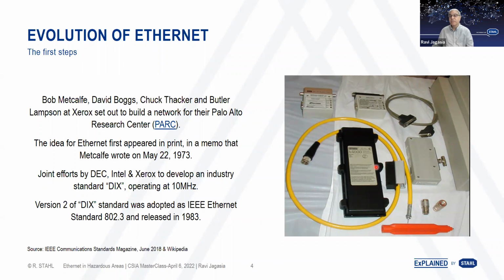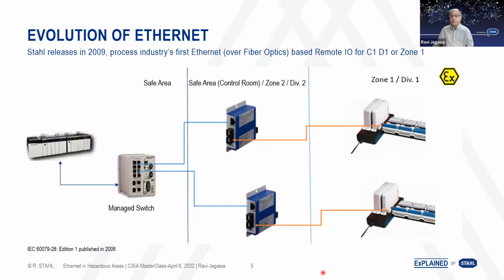Just some images here to realize what do we have or what we were working with previously when we talked about Ethernet and how compact the electronics is today. Going forward, STAHL did come up with a hazardous area solution with Ethernet, but with fiber optics. This was based on an IEC standard published in 2006, and in 2009 we came out with the first hazardous area installable remote I/O with an Ethernet interface, of course over fiber optics. So what you see is the fiber optics here, and then the standard cable going to the switch and going into your control system. This could be installed in zone 1 div 1, and these could be installed in the zone 2 div 2.